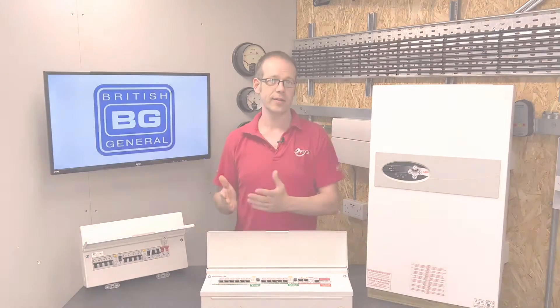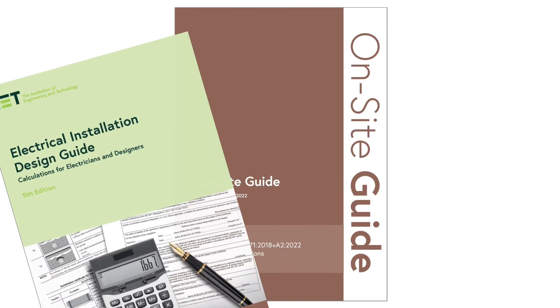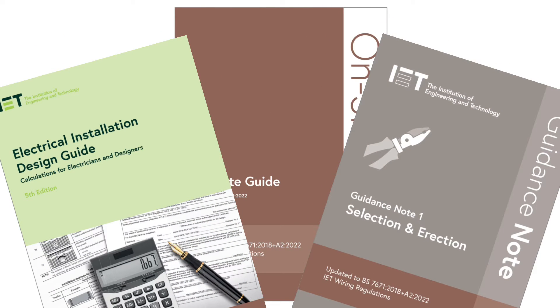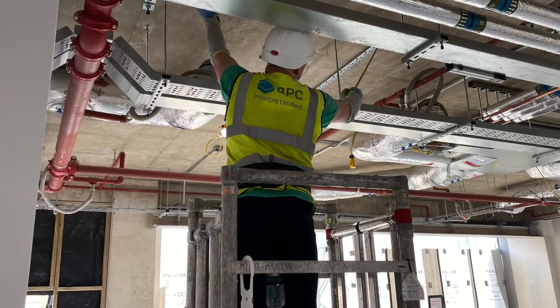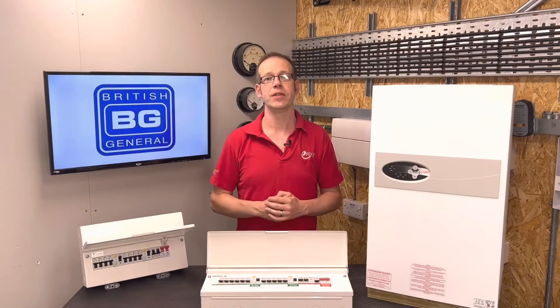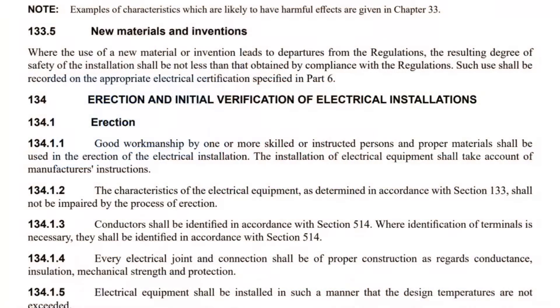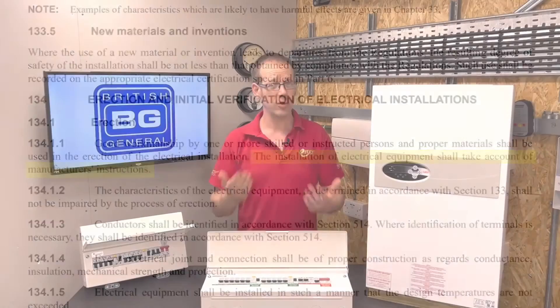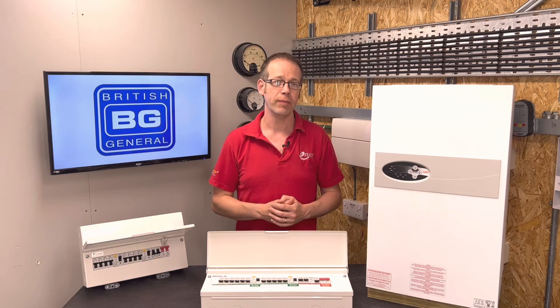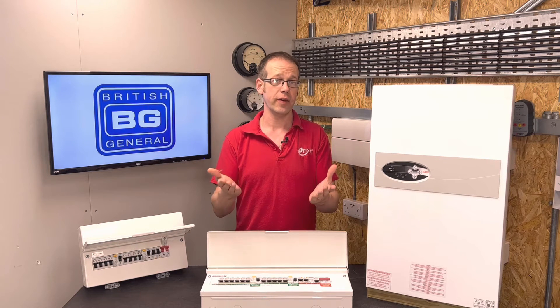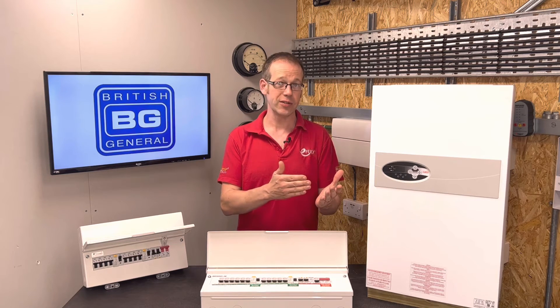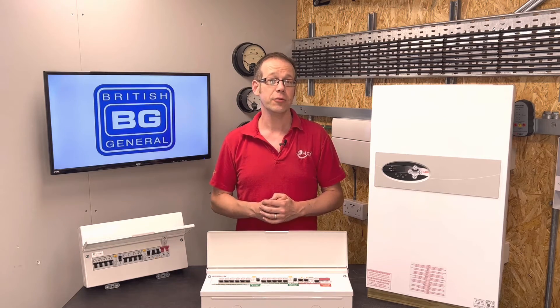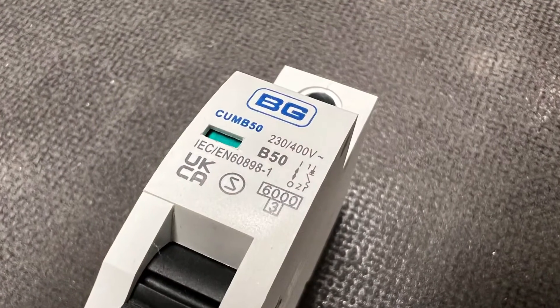We need to keep in mind that a lot of the IET publications have the word 'guide' or 'guidance' in the title — the On-Site Guide, Electrical Design Guide, Guidance Note 1 — and that's important. While the information in these books is valuable and working from it will help keep installations safe and compliant, there may be times when we go a bit beyond what they say. In fact, BS 7671 states in regulation 134.1.1 that the installation of electrical equipment shall take account of manufacturer's instructions. Having looked at the calculations using both the 40 amp and the 50 amp MCB, it actually makes no difference to the cable size, so we'll go with the manufacturer's recommendation: a 50 amp MCB.